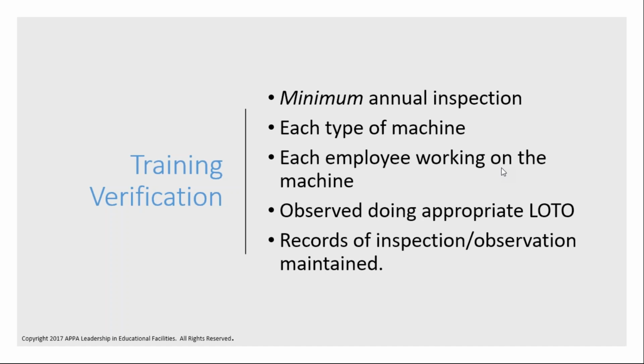And if there was no annual PM planned, you still have to go through the lockout tagout steps to make sure the equipment can be de-energized correctly. You know, and some of this makes sense because it's important in the event of an emergency that the worker must de-energize the equipment in order to be safe. Really, the goal is to make this all seem like second nature, like walking. But the trouble is the apparent amount of workload associated with it. So fortunately, one of the things that we wrote about in the article was that there's an easier way to tackle this problem and be compliant with the rules. So let's talk about that.